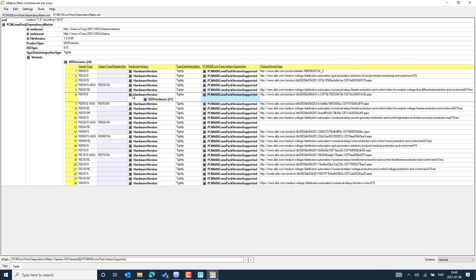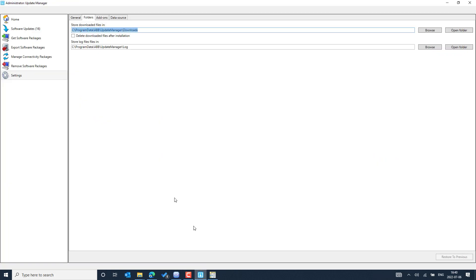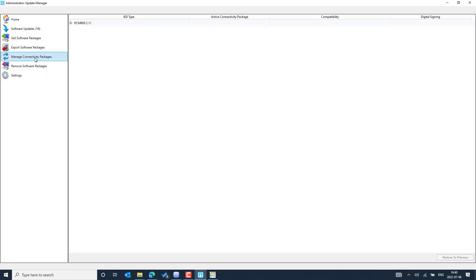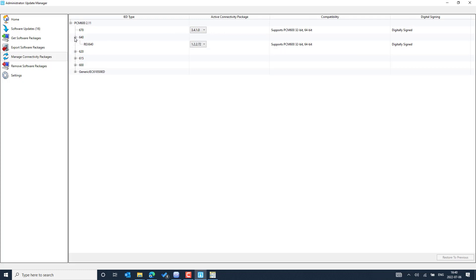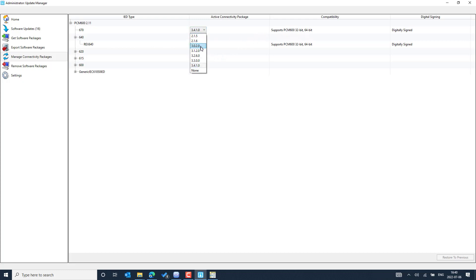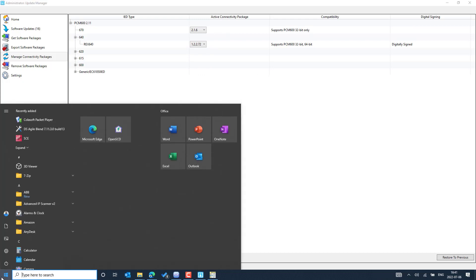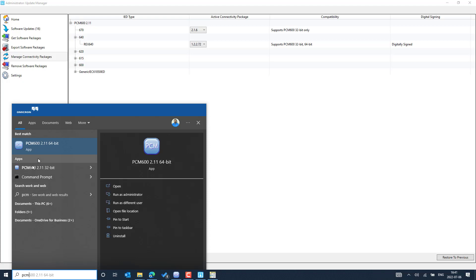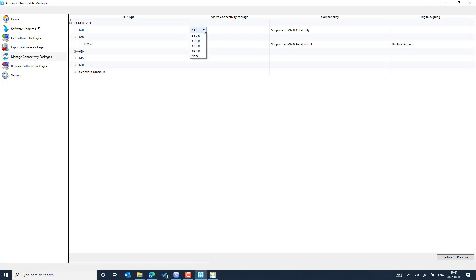One important point: if you have an old version of IED module and hardware version installed, some older compact versions do not support 64-bit, so you cannot open PCM600 and communicate with those old IED versions. In that case, you can go to 'Manage Connectivity Package,' expand PCM600 2.11, and check: the latest compact version for 670 supports both PCM600 32-bit and 64-bit, while older compact versions only support 32-bit PCM600. In that case, from the Start menu under PCM600, there will be a PCM600 2.11 32-bit compatible application that you need to use with old IED versions.